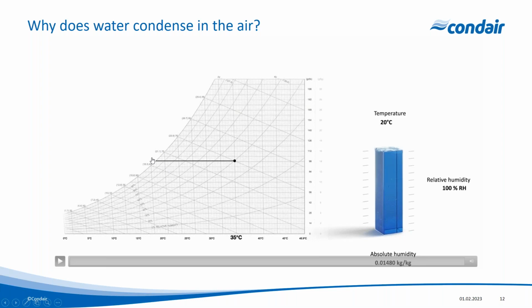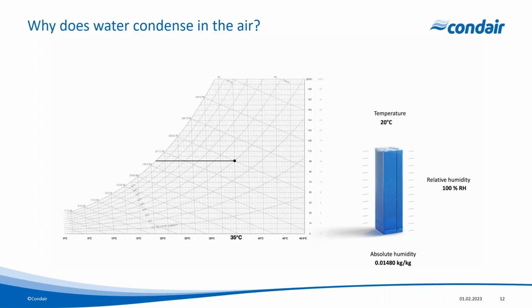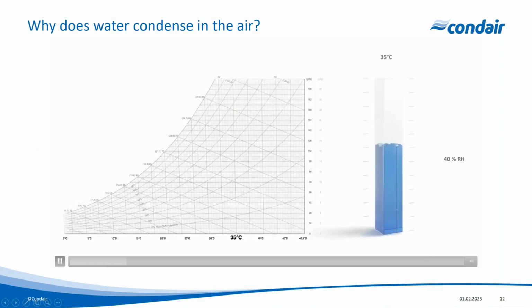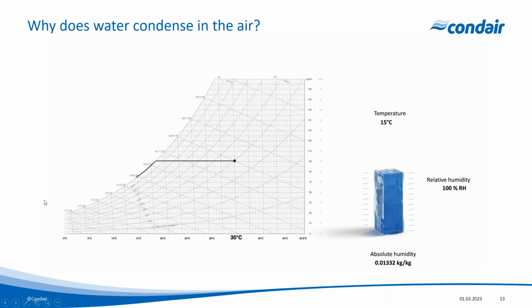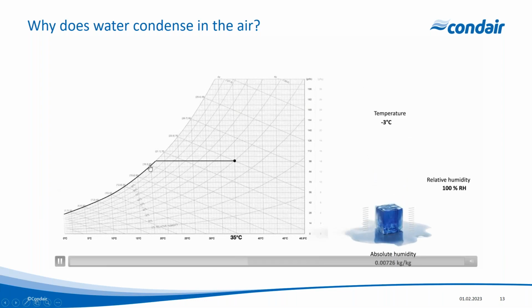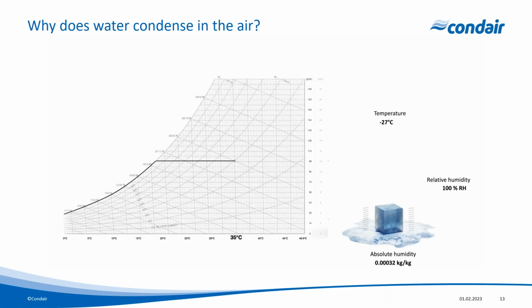And at this point, well, we've come down to 21 degrees C on our chart. And I'm now 100% saturated. But I don't want my cold store or my freezer store to be 20 degrees C. I want it to be much colder than that. So what happens then is that we go through our first phase of cooling, we've reached saturation, and we then cool further. And as we follow that curve down, the temperature drops, but of course the air can't hold as much moisture. So moisture falls out of the air.